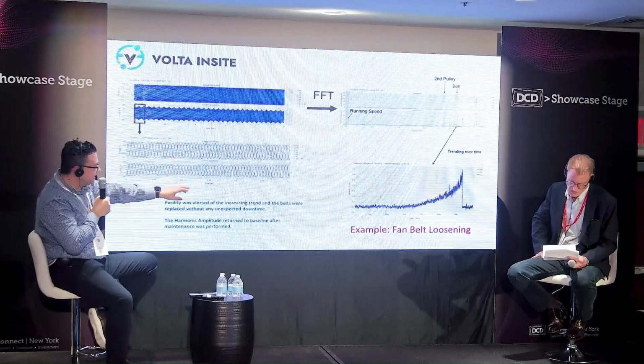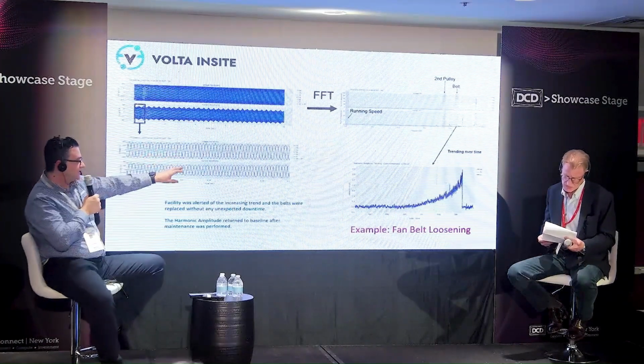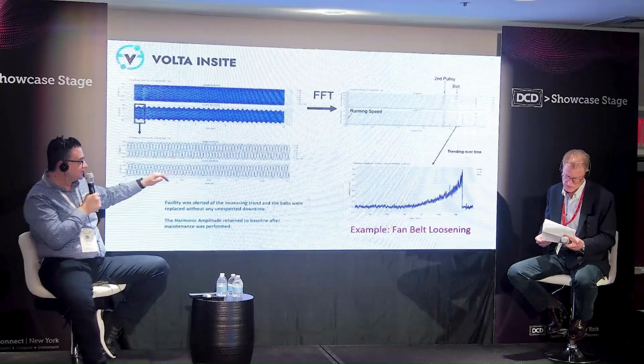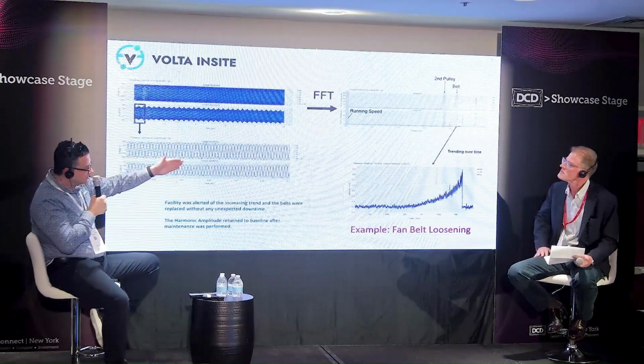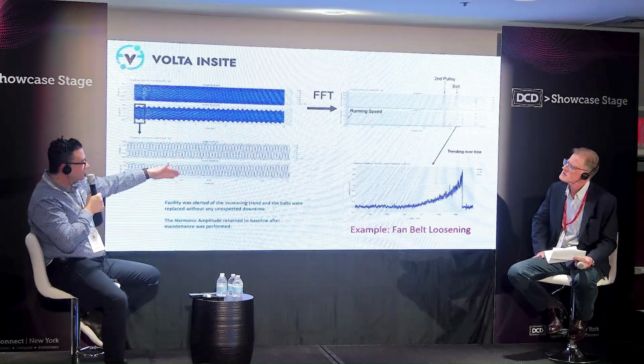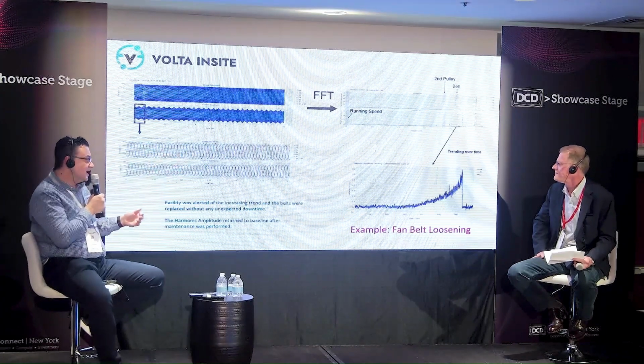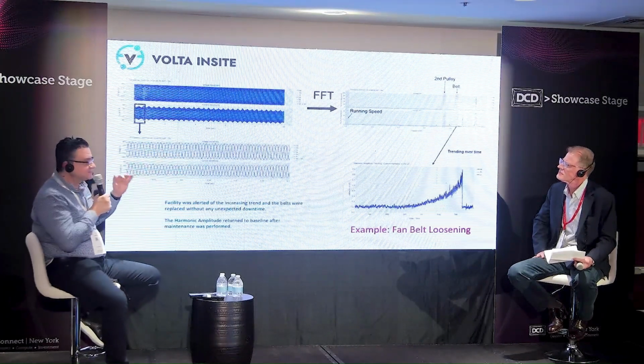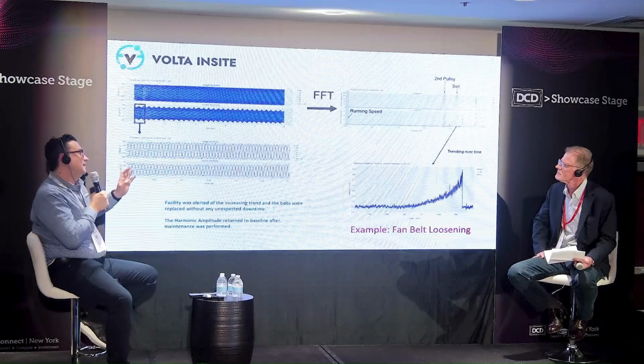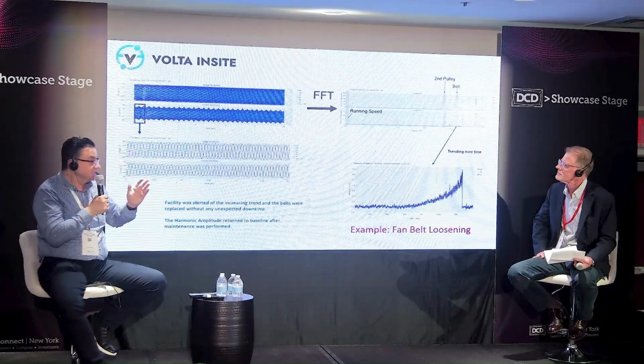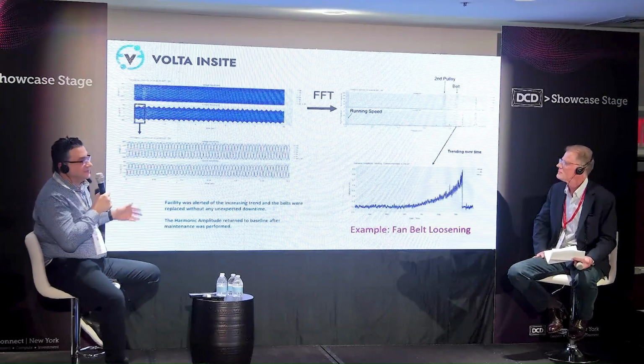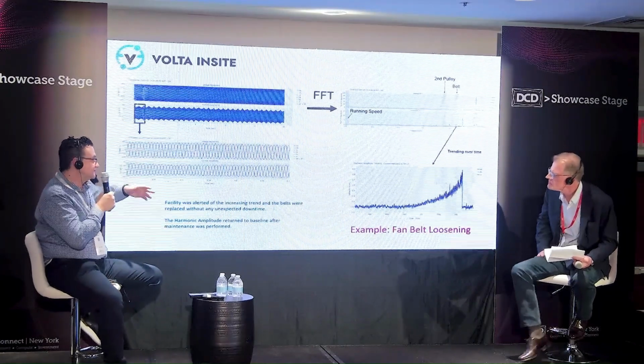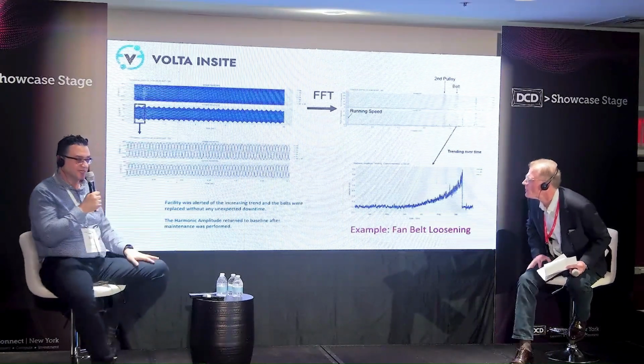In this particular case, we're showing an example of a fan belt getting looser over time, so the amplitude of that harmonic is trending upwards. And how do you come up with that harmonic? It's a basic geometric calculation to map back to the operating synchronous speed of the motor, for example.